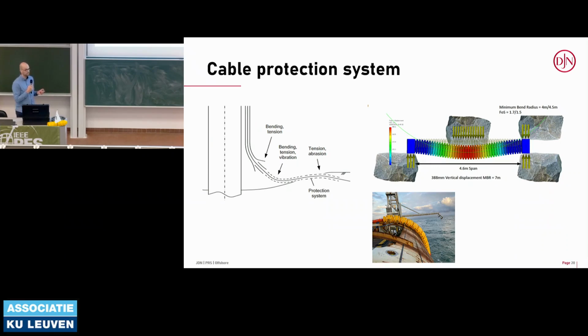The free span between those rocks is almost 4.5 meters. On top of that, we also need to protect the cable, so we need to drop rocks on top as a stabilization layer. The higher you go toward the surface, the greater the forces and currents will be, so if this is a 3 to 6 ton layer, imagine what needs to come on top of it.